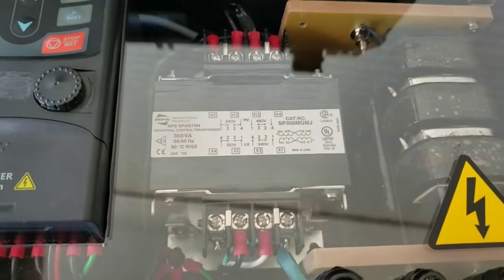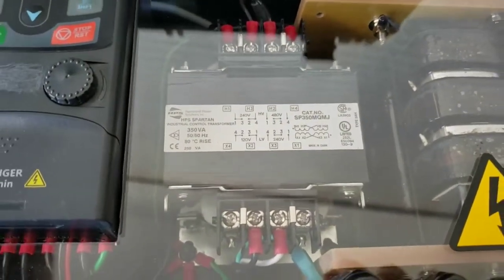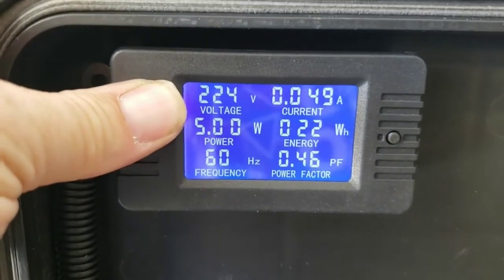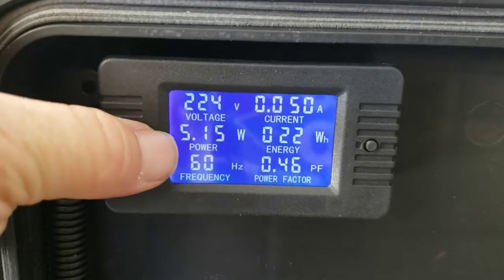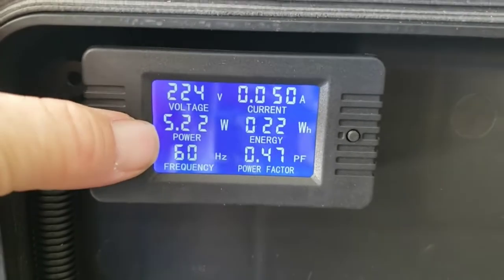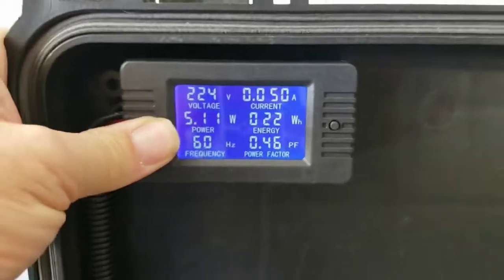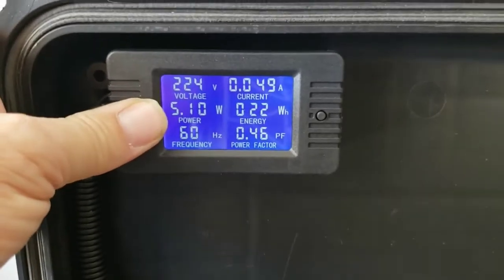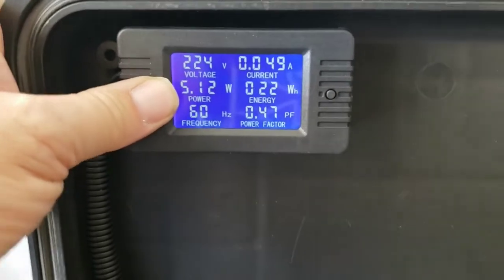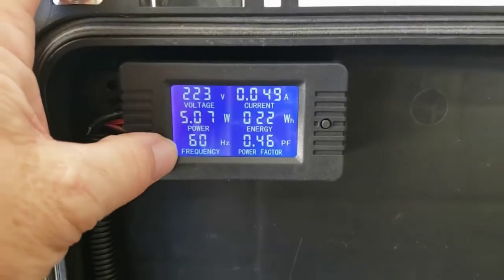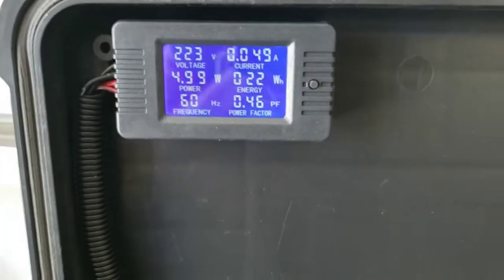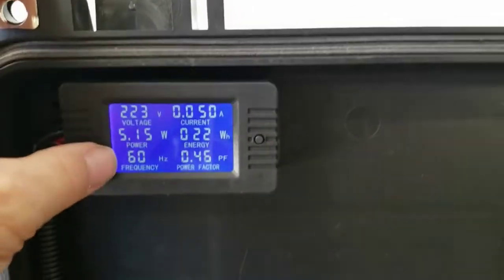That is the voltage after the step-up transformer. That transformer down there in the middle goes from 120 to 230 or 240. In this case, I'm getting 224 out of it. Just below that, we've got our wattage showing. The way I'm generally tuning these is to go up to roughly 400 watts on a good cell. That can vary depending on the condition of the cell. Gas pressure and things like that can alter that.